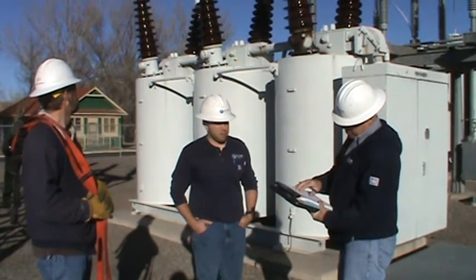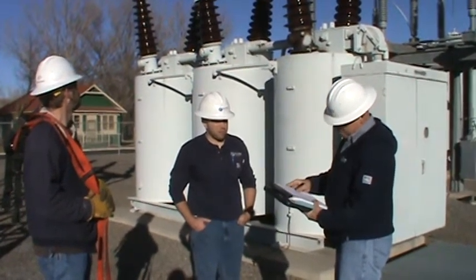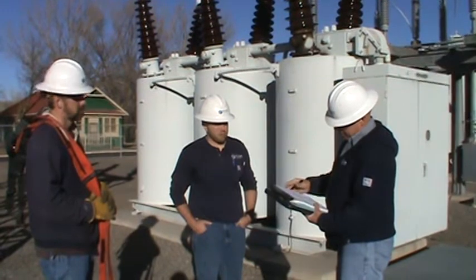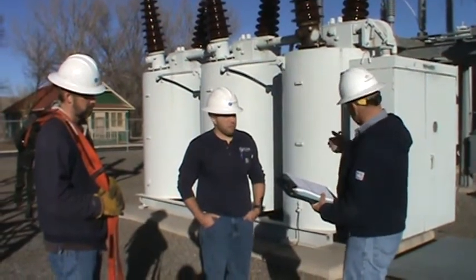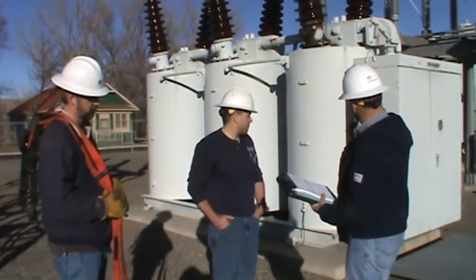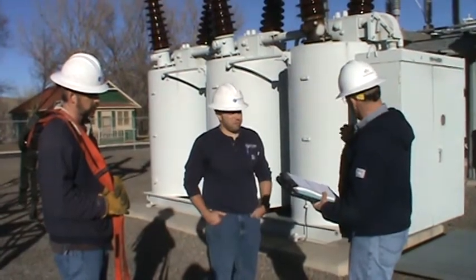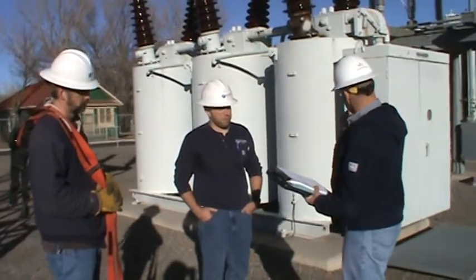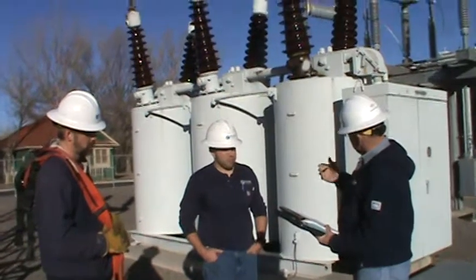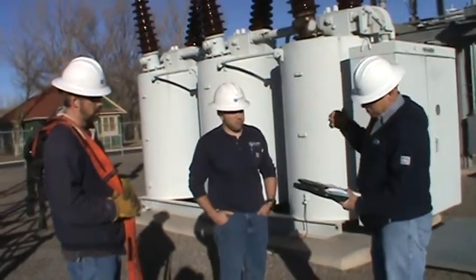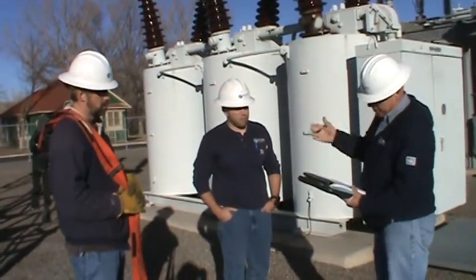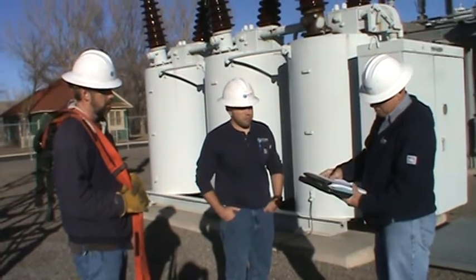So oil maintenance is going to be covered under safety manual 131. Make sure we've got communication awareness, gentlemen, when we're doing our oil maintenance. Make sure that somebody's watching the oil flow from the tanker, from the breaker into the truck. Make sure that we keep a mind on when we go to put the oil back in the breaker, somebody that's keeping an eye on that so we don't have any oil spills.